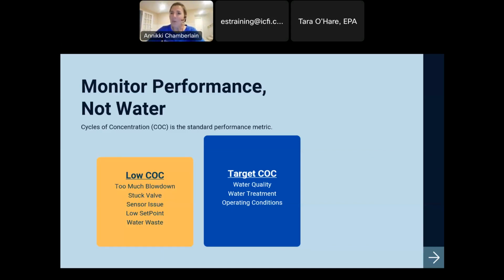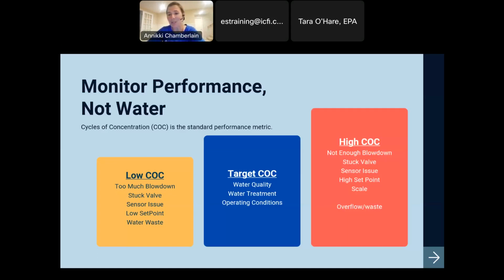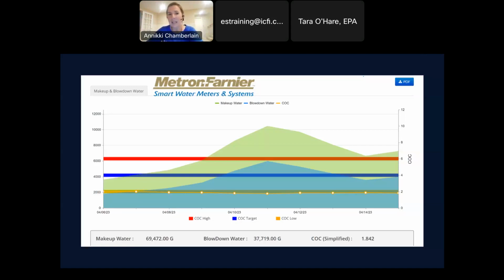Then I'm going to say, okay, what's my low threshold? So let's say my target is 4. If I get below 2, I think something's pretty wrong. That's a pretty big departure. Again, too much blowdown, stuck valve, sensor issue. We're going to look at some case studies, of course. Or if I get above my high threshold, again, I probably have a mechanical problem. But as long as I'm in between those thresholds, I'm good to go. The tower's just using as much water as the tower is going to need. So this is a dashboard, again, done by Metron Farnier Water Scope.